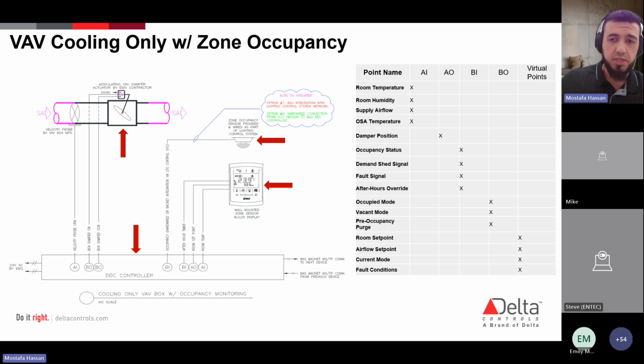So again, there's your DDC controller. Now your DDC controller, at least for the VAV space, will be connected to a wall-mounted temperature sensor, right? With integral relative humidity sensor. Okay, and now it says temperature sensor. It doesn't say thermostat, but I see a slider here, so it's probably also a thermostat. So you can adjust the output from here, or you can adjust it through the controller, right? Through your sequence of operations, right?